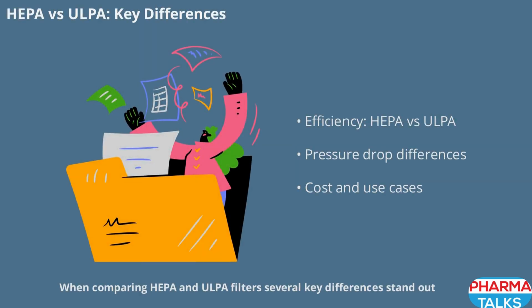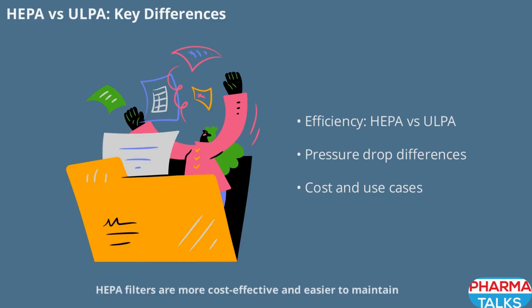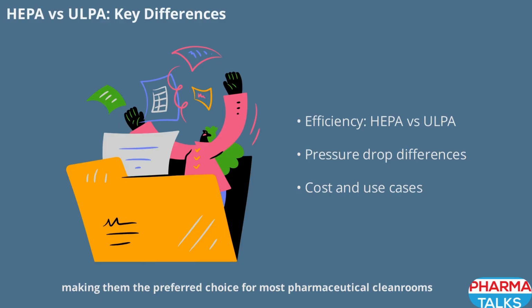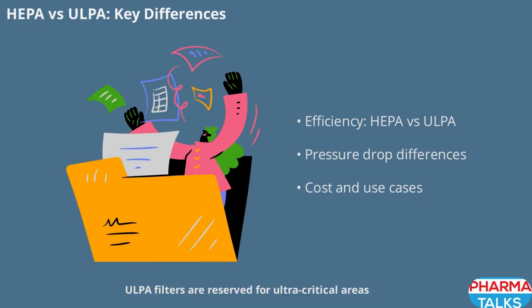Comparing HEPA and ULPA filters, several key differences stand out. HEPA filters offer 99.97% efficiency at 0.3 microns, while ULPA filters provide 99.9995% efficiency at 0.12 microns. ULPA filters are more efficient but also create a higher pressure drop, requiring stronger HVAC systems and increasing energy costs. HEPA filters are more cost-effective and easier to maintain, making them the preferred choice for most pharmaceutical cleanrooms. ULPA filters are reserved for ultracritical areas where the highest level of cleanliness is essential.